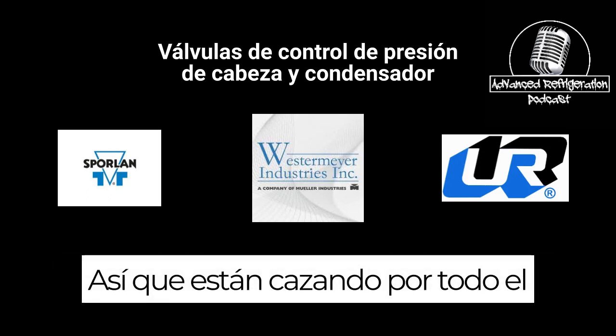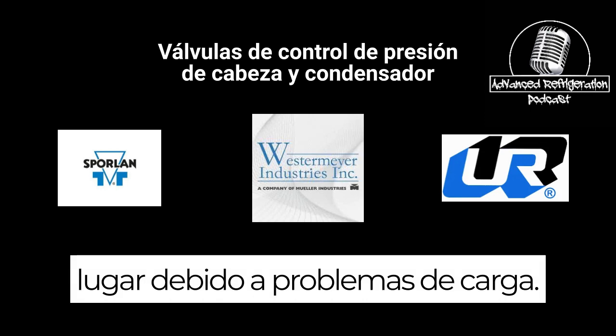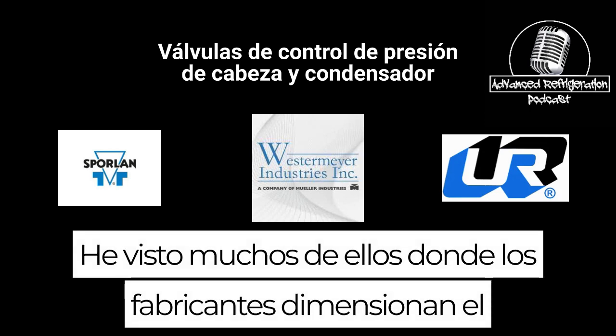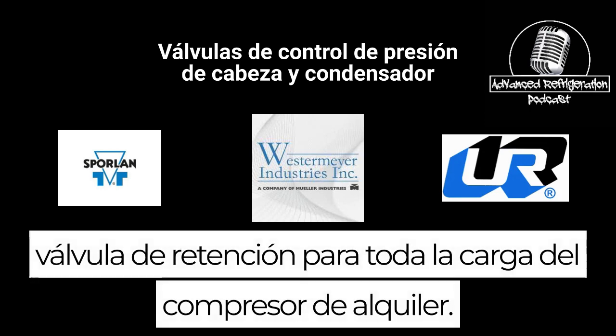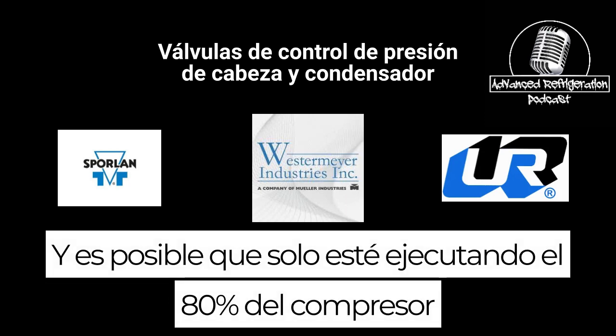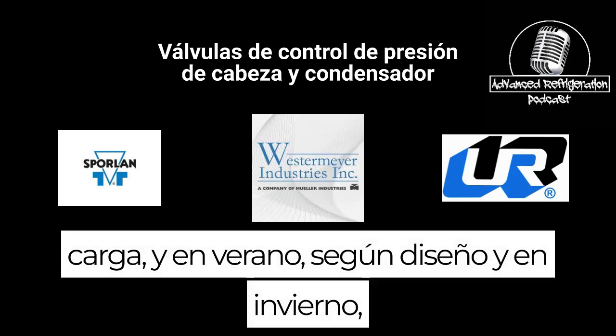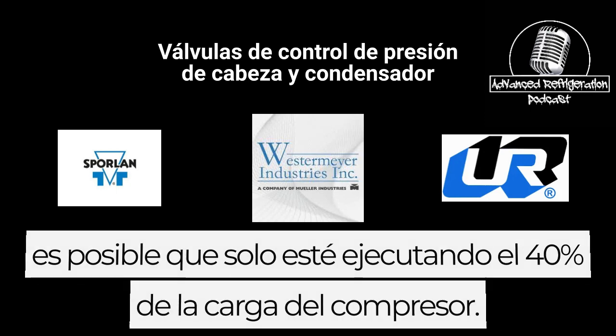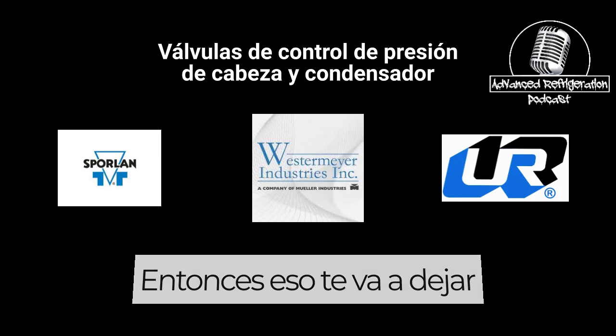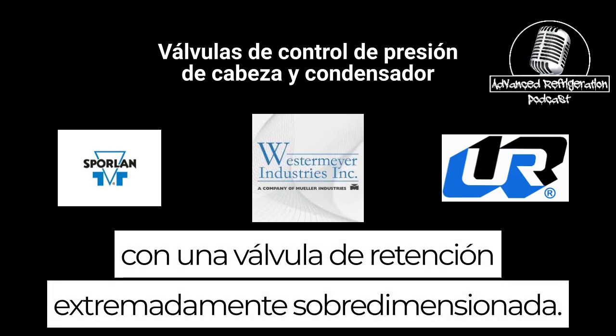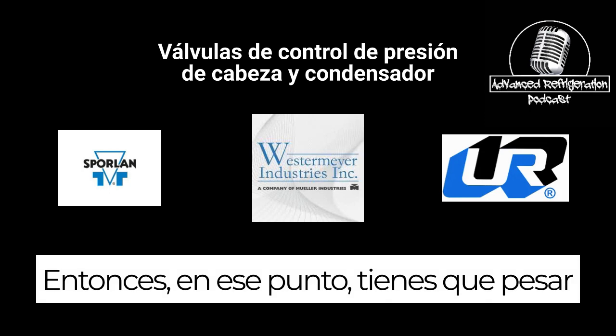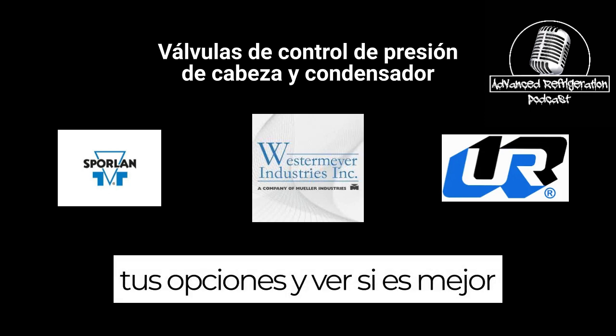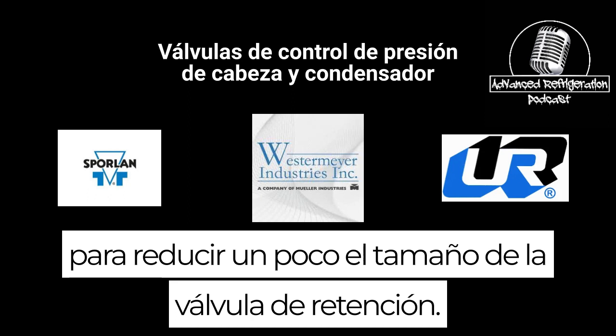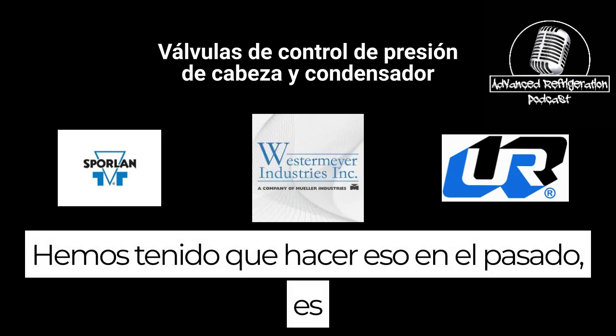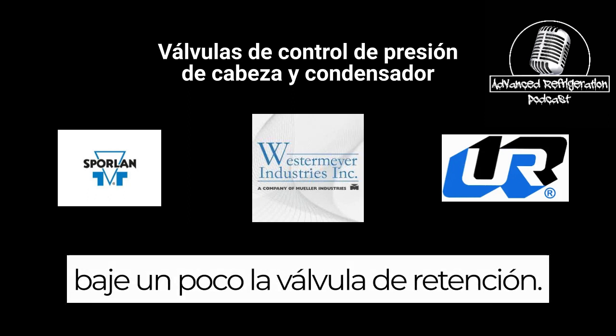So they're hunting all over the place. It could be because of load issues. I've seen plenty of them where manufacturers size the holdback valve for the entire rack's compressor load, and you may only be running 80% of compressor load in the summertime per design, and in wintertime you may only be running 40% of compressor load. That's going to leave you with an extremely oversized holdback valve. At that point, you've got to weigh your options and see if it's better to undersize the holdback valve a little bit. We've had to do that in the past, drop the holdback down a little bit.